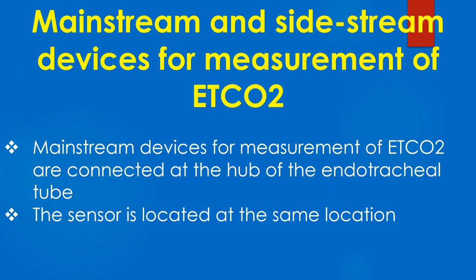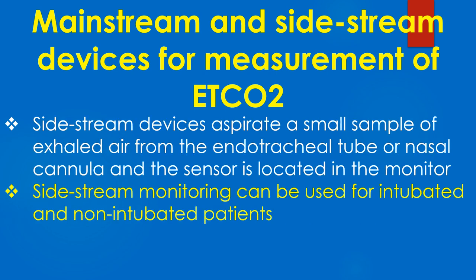There are mainstream and sidestream devices for measurement of ETCO2. Mainstream devices are connected at the hub of the endotracheal tube, and the sensor is located at the same location. Sidestream devices aspirate a small sample of exhaled air from the endotracheal tube or nasal cannula, and the sensor is located in the monitor. Sidestream monitoring can be used for both intubated and non-intubated patients.